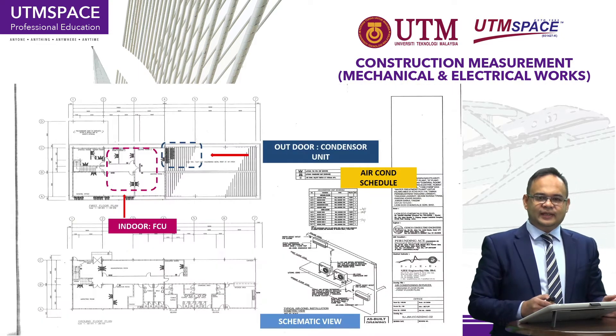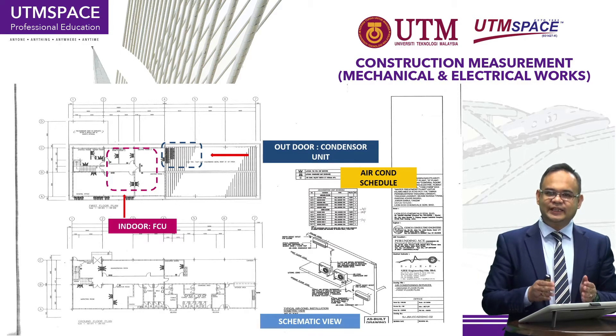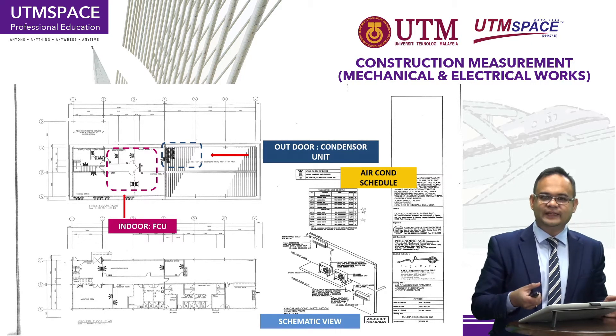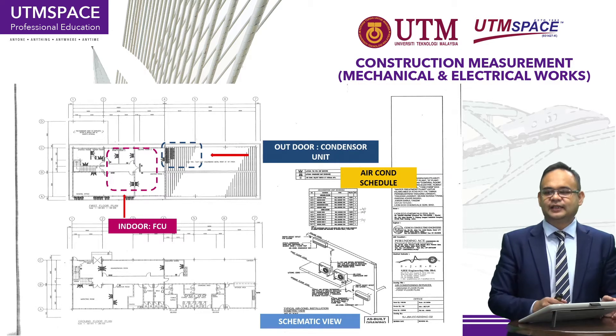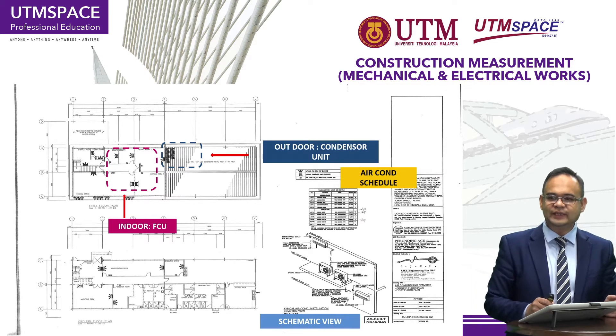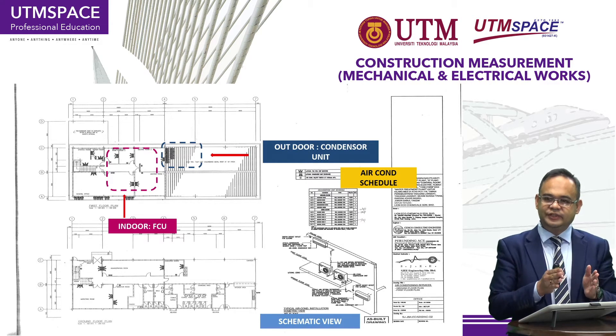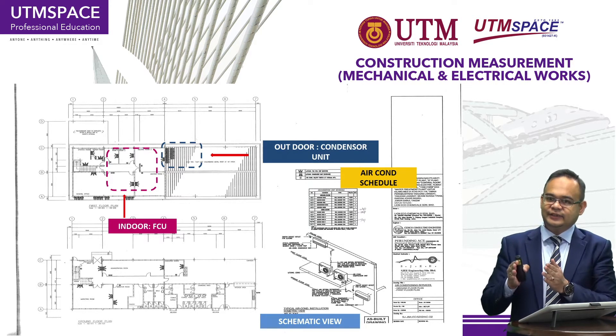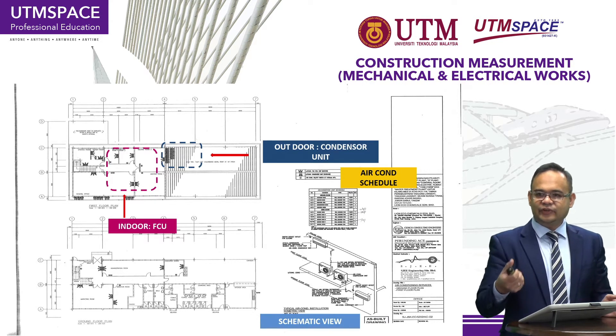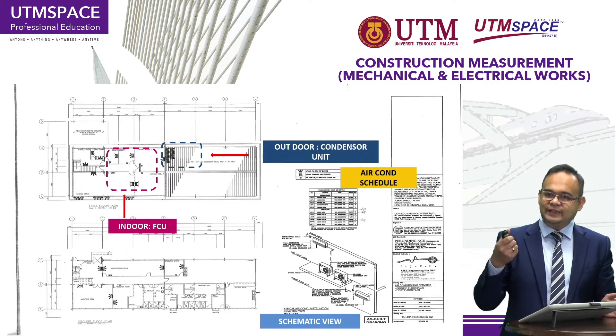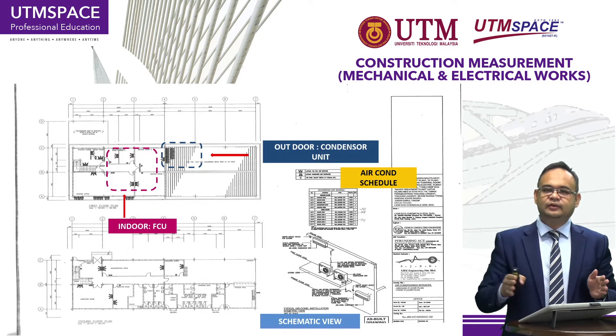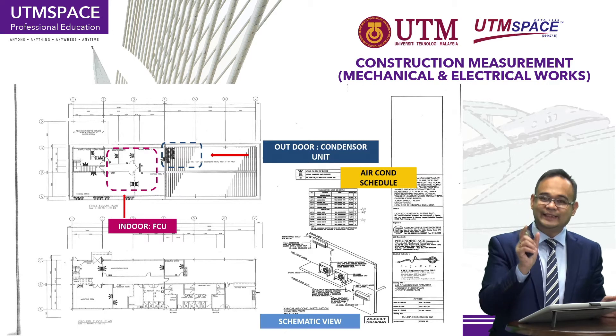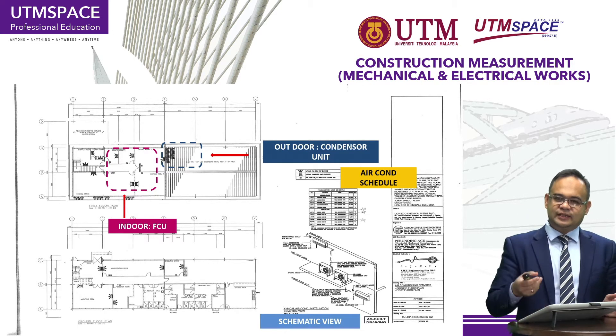Normally, engineers will communicate with us using drawings. Engineers will tell us what type of components and equipment are used for air conditioning installation in buildings using what we call an air conditioning installation layout. This is an example of a layout drawing, which shows first the location of the equipment, and second the air conditioning schedule, which contains the location of that particular equipment, the cooling capacity, and the type of air conditioning — whether it needs to be installed on the wall or inside the ceiling.